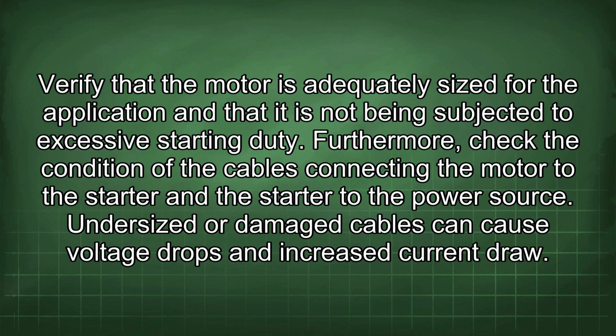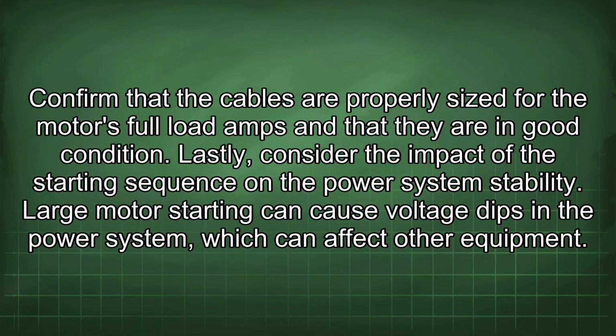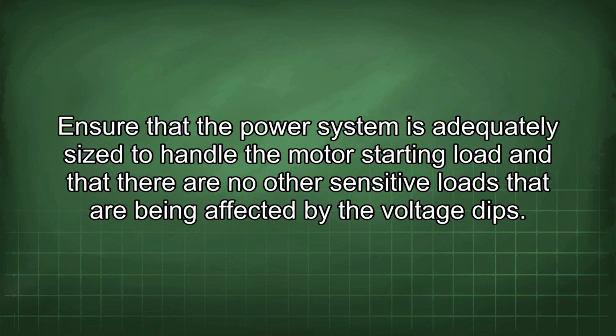Furthermore, check the condition of the cables connecting the motor to the starter and the starter to the power source. Undersized or damaged cables can cause voltage drops and increased current draw. Confirm that the cables are properly sized for the motor's full load amps and that they are in good condition. Lastly, consider the impact of the starting sequence on the power system stability. Large motor starting can cause voltage dips in the power system, which can affect other equipment. Ensure that the power system is adequately sized to handle the motor starting load and that there are no other sensitive loads that are being affected by the voltage dips.